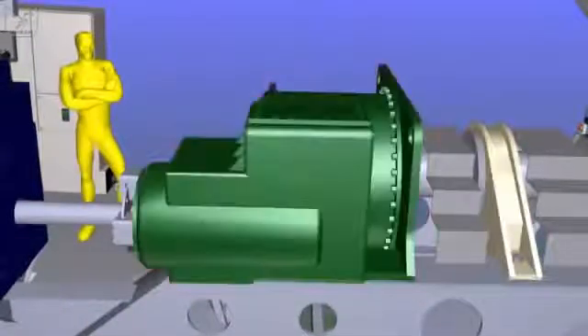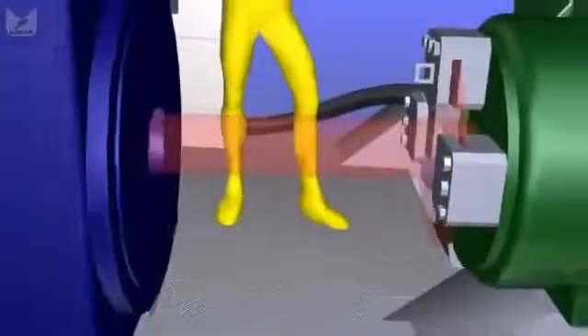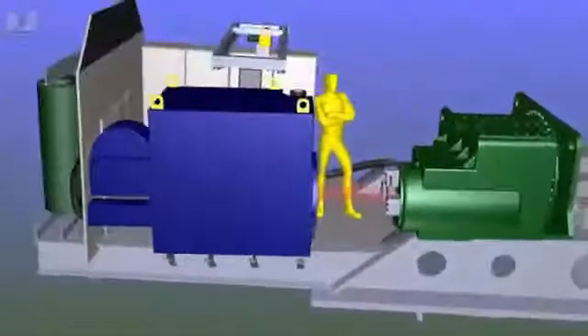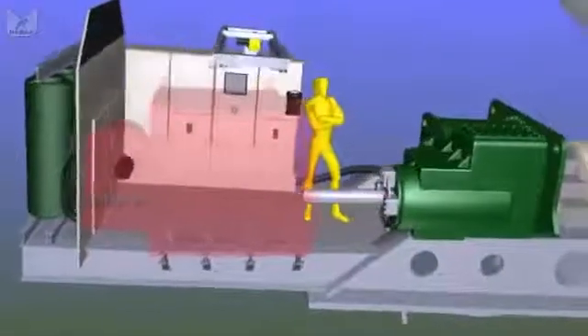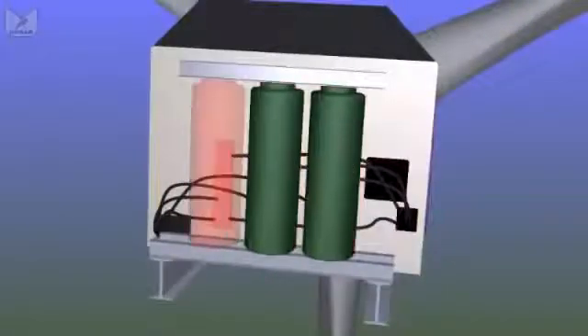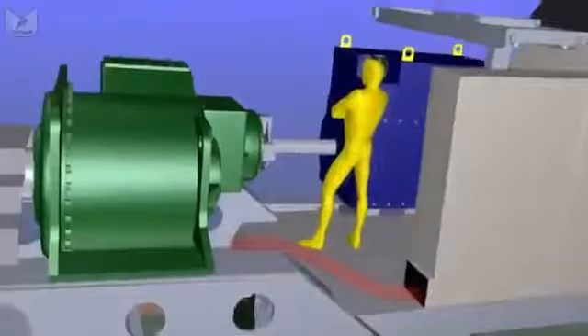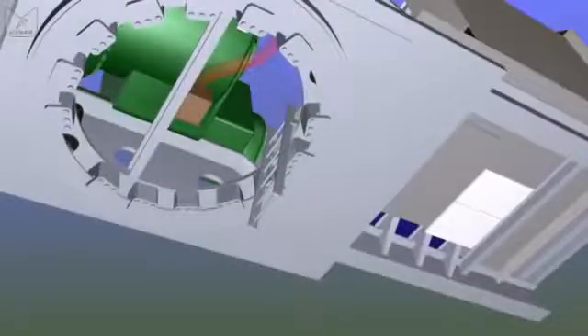Our main shaft drives our gearbox which is mounted centrally because it's often the heaviest component. Out of the back comes a high speed shaft as before, that's where the braking system is. High speed shaft then drives the generator which is usually oil filled. The generator then supplies 690 volts, in this case into our transformer which is sitting right next to it. That high voltage signal then passes through the switch gear and the cabinet, down the dropper cable, straight down to the bottom of the tower, through those switches on platform 2 and off to the substation.